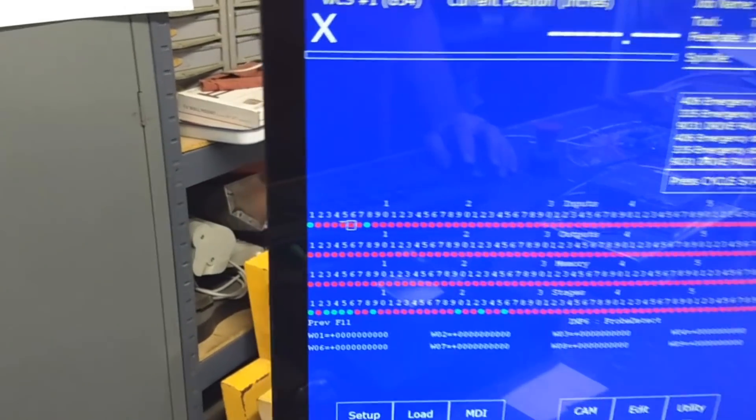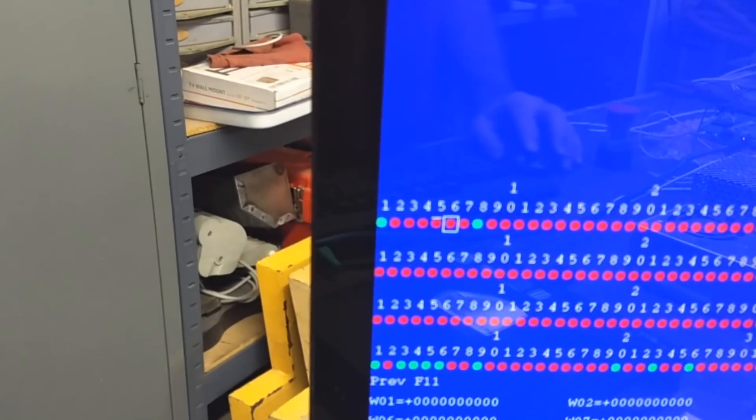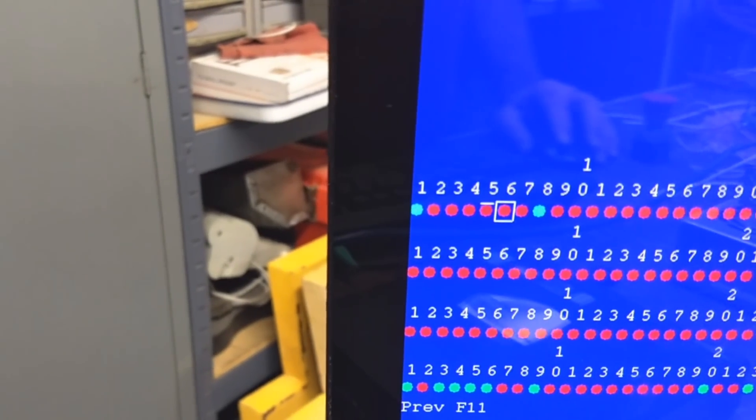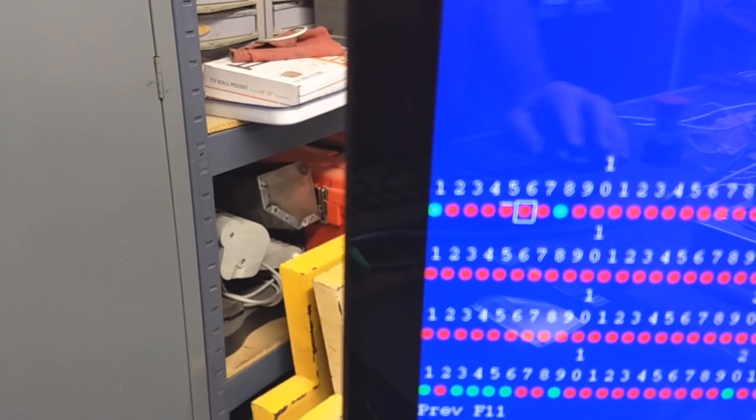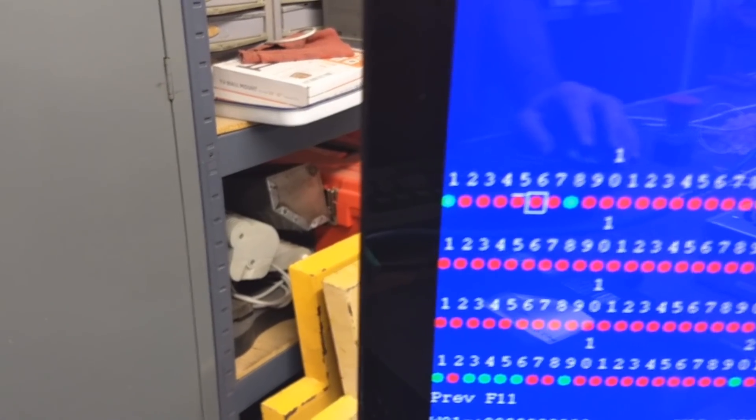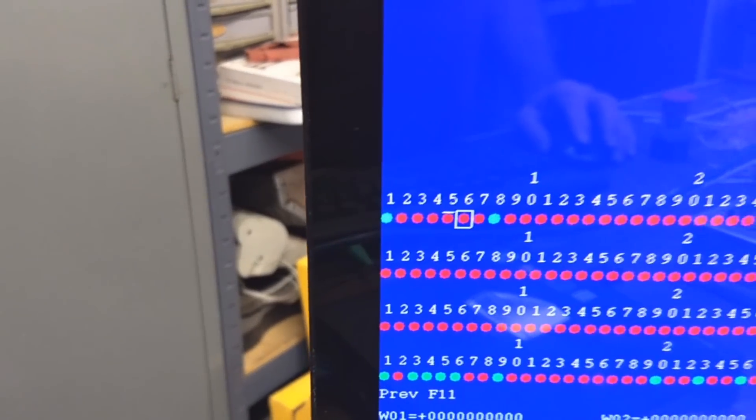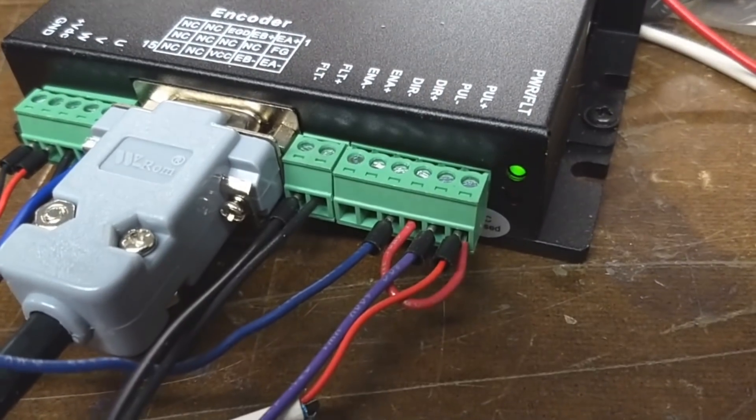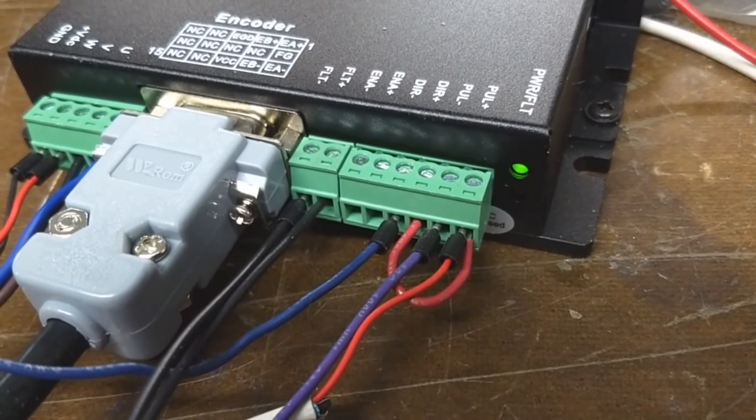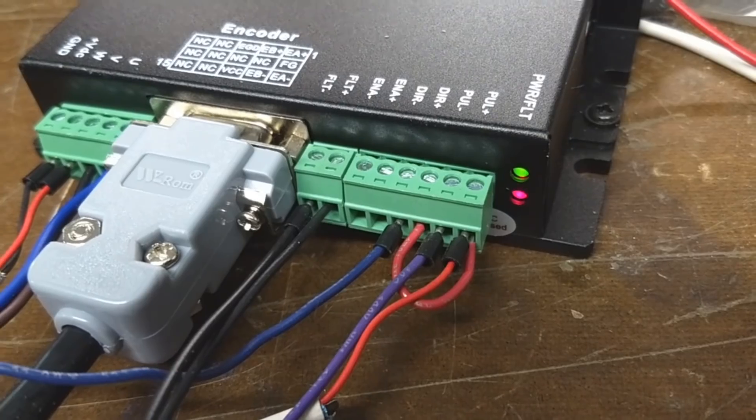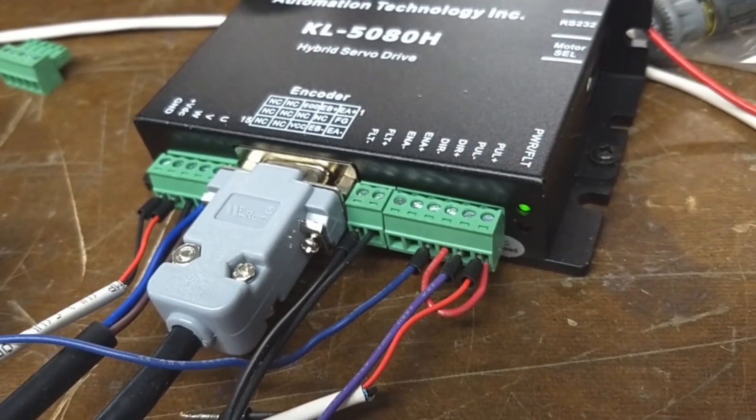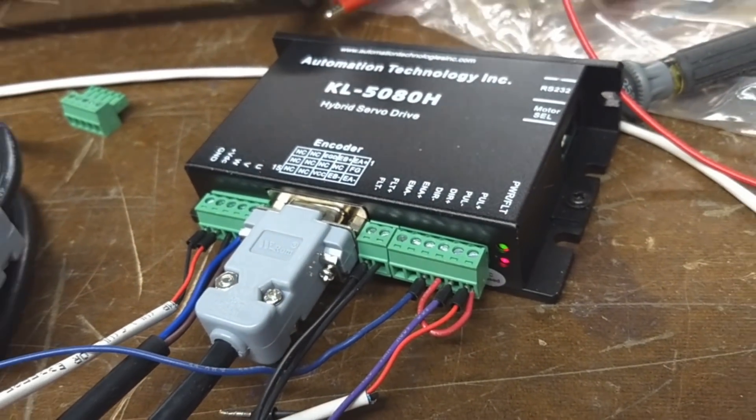And you see right there, the fault LED went out. And then if you go over here to the drive, you see the fault LED flickering there. Now the only way to reset that is to power down the drive.